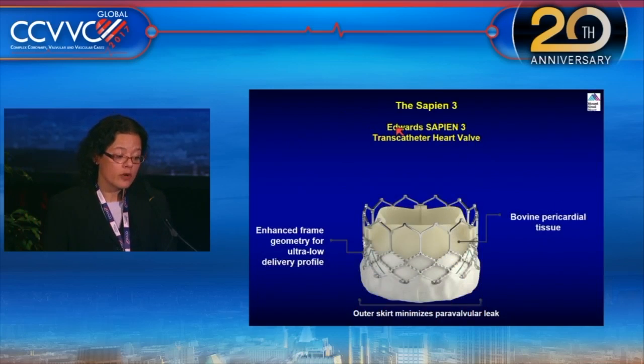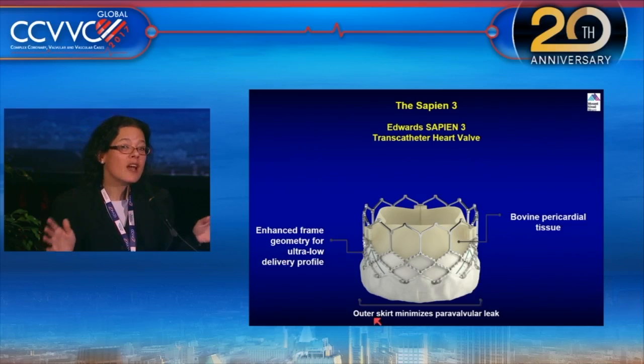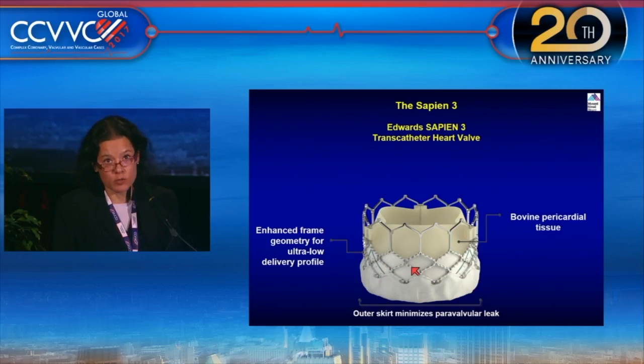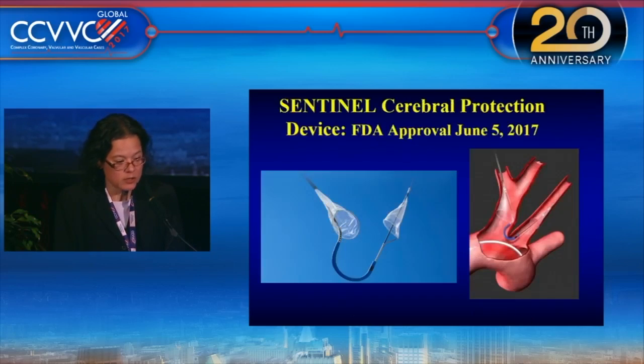This is the Sapien 3. This is the third generation Sapien device that's approved. It's still chromium cobalt, but thinner struts for better apposition and better endothelialization. It's still bovine pericardial tissue and balloon expandable. You can see they added an outer skirt, and this is to have a better seal and prevent the paravalvular leak. It's a 14 French sheath, so they did go down with that, so reduce bleeding and vascular complications. And again, what I had just said with the Pro, with this, we've seen an increase in the need for pacemaker in this newer generation Edwards because of this outer skirt and the way it can affect the bundle branches.